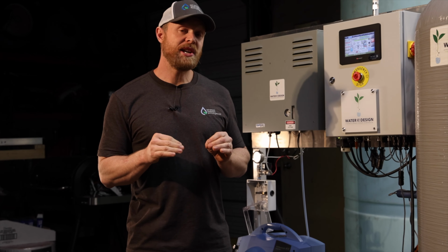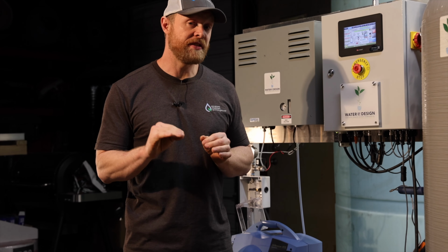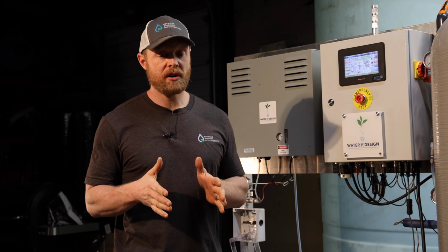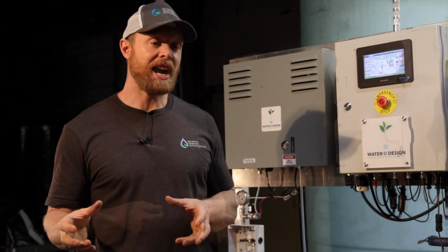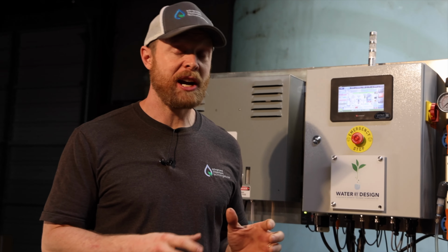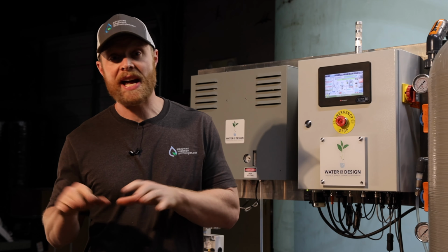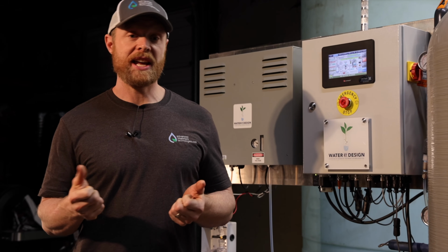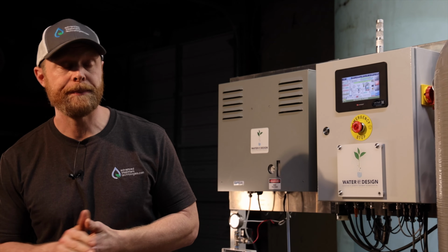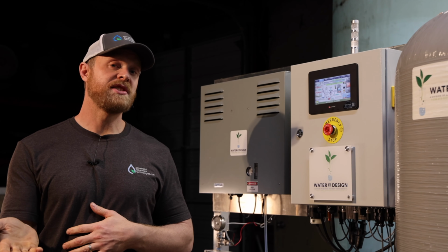By doing the CIP cycle as the last event of the day, what you're doing is making sure that you're not just leaving a whole bunch of highly oxygenated water sitting in those lines overnight, because that is the very environment that's going to grow biofilm. So by sending that highly ozonated water with most of that oxygen still being in the form of ozone, you're going to effectively kill everything in that line, and then that water can sit in there overnight, and it's going to be way less problematic than if you leave just oxygen sitting in that line overnight. So again, we recommend that you do it as the last event of the day.